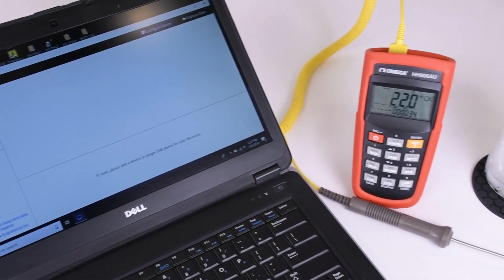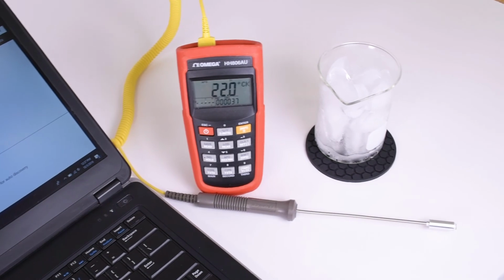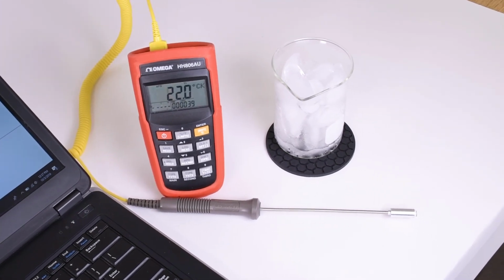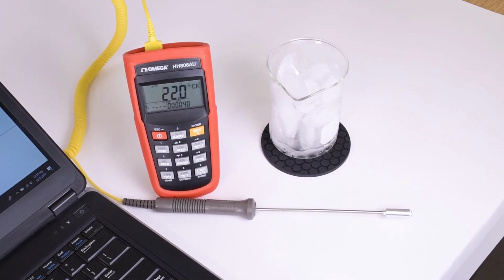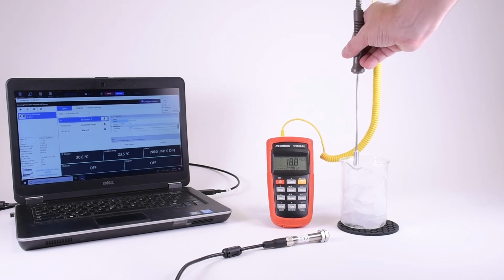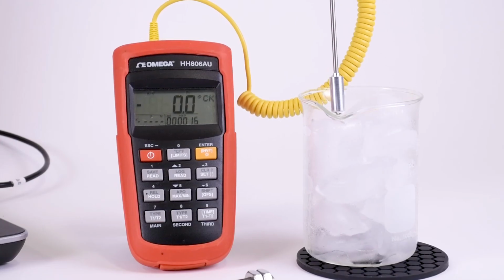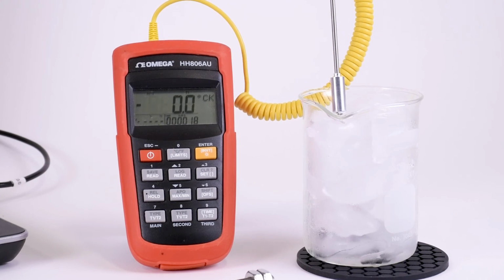Now that we've got our sensor up and reading, it's time to calibrate. To help us calibrate our smart probe, we're going to use an ice bath to achieve a known temperature of 0 degrees Celsius. Now we'll verify the temperature with this surface probe. And sure enough, we've got 0 degrees Celsius.